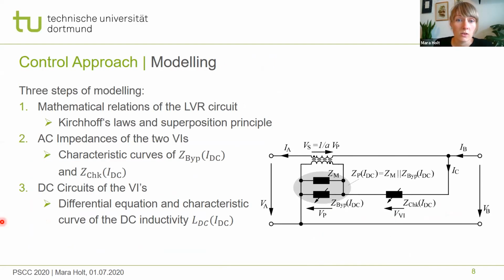To develop a closed loop control based on the control path, the line voltage regulator is modeled in detail. The modeling is divided in three parts. First, the circuit of the line voltage regulator and its mathematical relations are determined based on Kirchhoff's laws and the superposition principle at the transformer. Next, the impedance of the variable inductors are determined. Their impedance depends on their control states. The relationships are modeled using characteristic curves measured on the line voltage regulator in the laboratory.